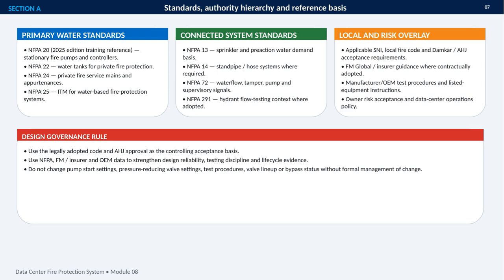These standards connect with other requirements. NFPA 13 supports sprinkler and pre-action water demand calculations. NFPA 14 addresses standpipes and hose systems where required. NFPA 72 governs water flow, tamper, pump, and supervisory signals, and NFPA 291 provides context for hydrant flow testing where adopted. Local SNI requirements, the applicable fire code, and Damkar or AHJ acceptance requirements also apply. FM Global or insurer guidance, manufacturer instructions, and owner operating policies may add further controls.